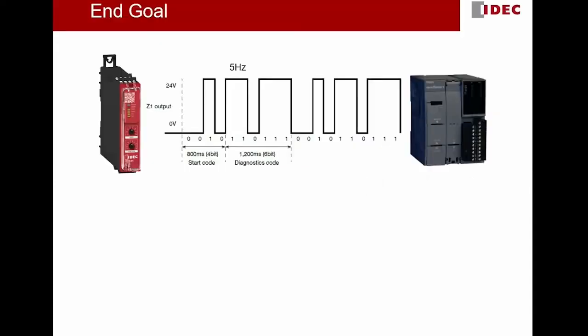So this is what we would like to achieve at the end of this tutorial. All HR6S safety relays from IDEC, regardless of the model, they all come with one terminal called Z-1. This Z-1 is constantly giving out a diagnostic pulse output, and this pulse output consists of the diagnostic information of the safety circuit and safety devices connected to this HR6S safety relay.